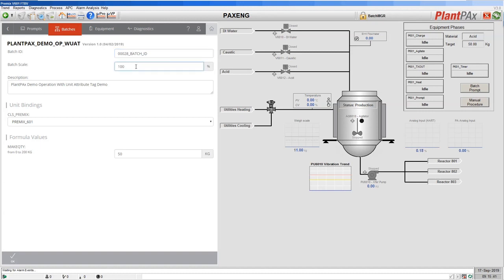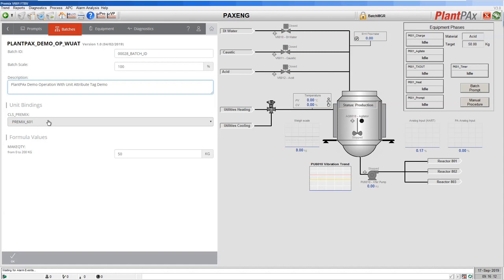Here we have batch scaling. In a batch recipe you can specify that some of your values or formula parameters can be scalable. If they are scalable, putting 200 in this box will double those values, and putting 50 will halve them. Here we can see a description of the recipe created by the recipe creator. Then we get down to the unit bindings. One key feature of FactoryTalk Batch is you can have class-based recipes.